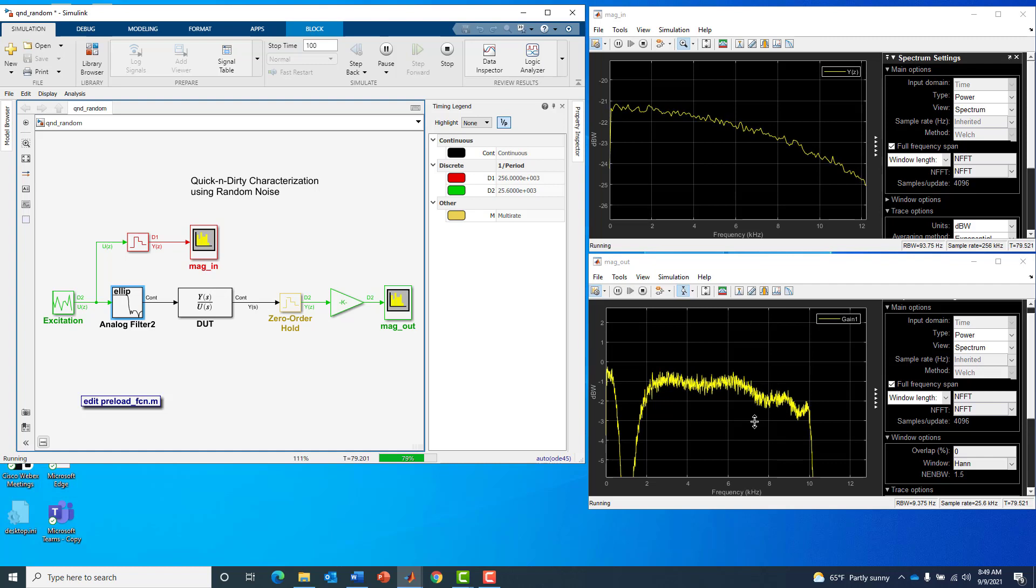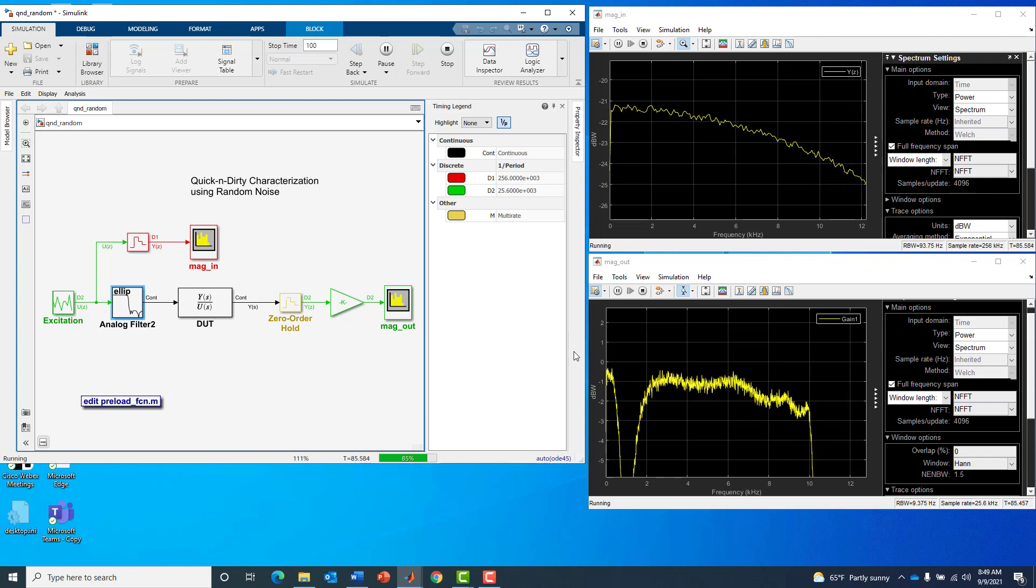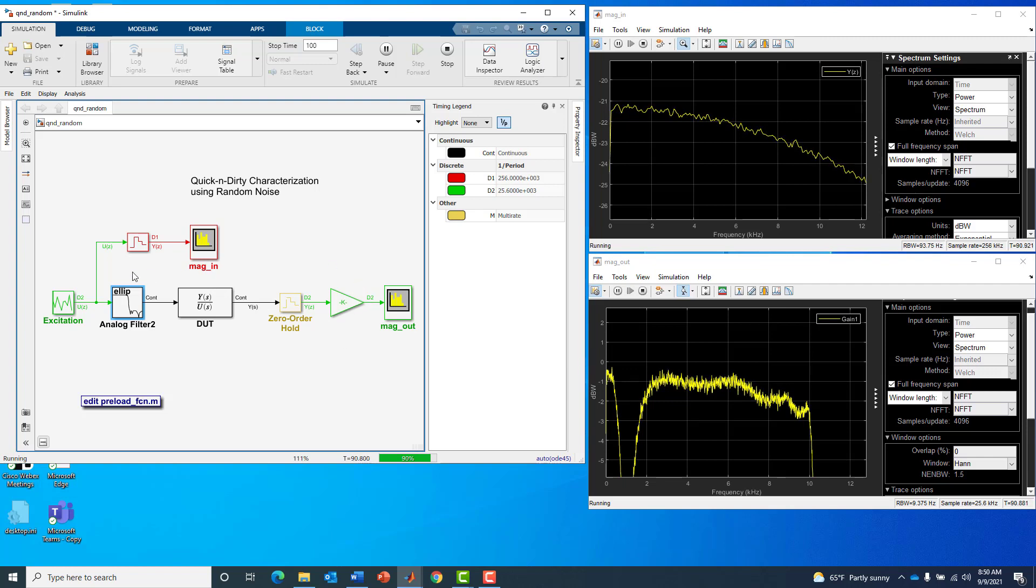We can't really completely avoid that with this limited measurement setup. We don't have phase in this measurement either. That's another downside, a casualty of this measurement setup. For phase, typically you measure it with respect to something, in this case the input. We're not measuring it or factoring it into this measurement.